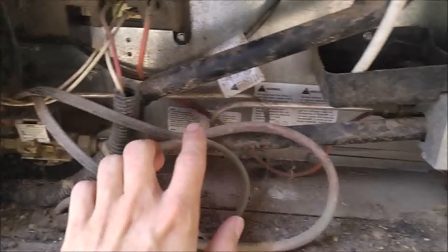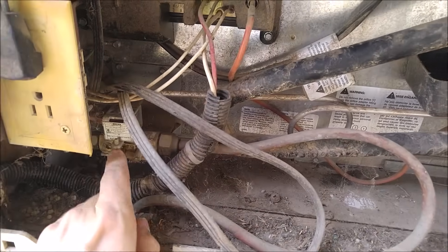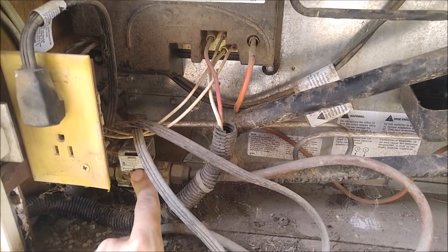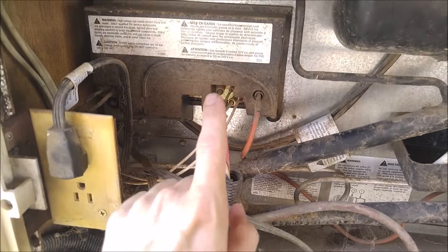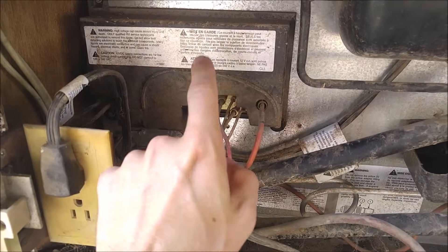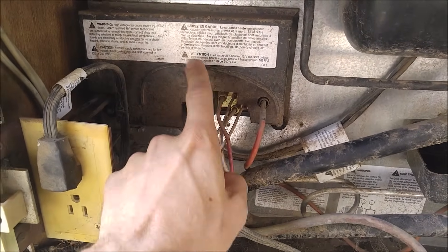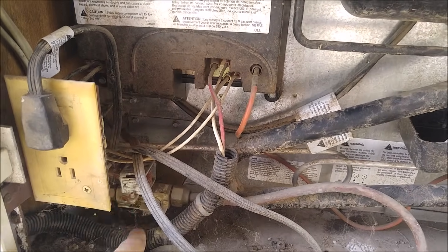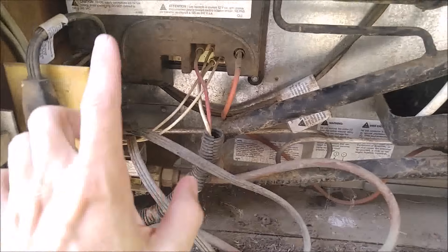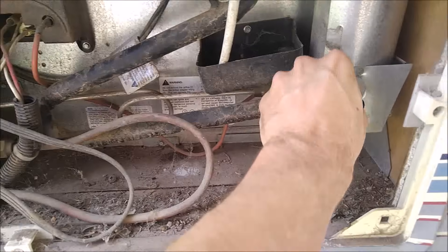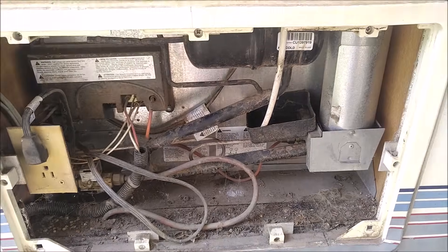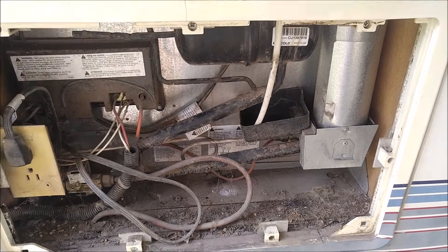If that doesn't fix it, come back here to your solenoid. You might have a solenoid problem. If that doesn't fix it, come back here to your control board. Make sure you're getting voltage to the solenoid. It's a simple system. Very easy to troubleshoot and very easy to fix.